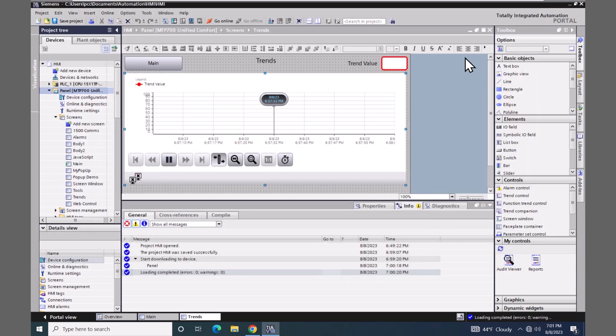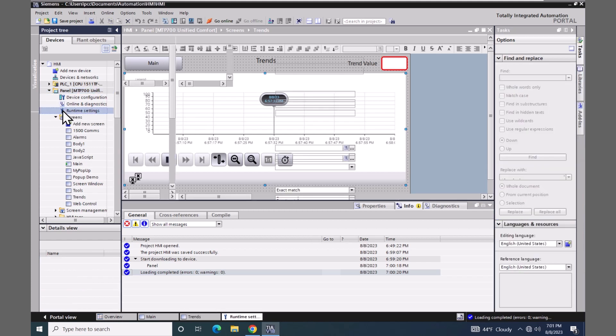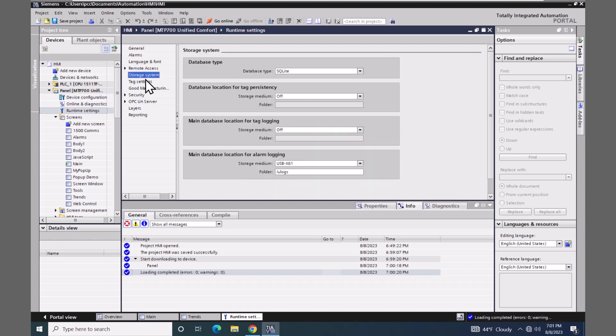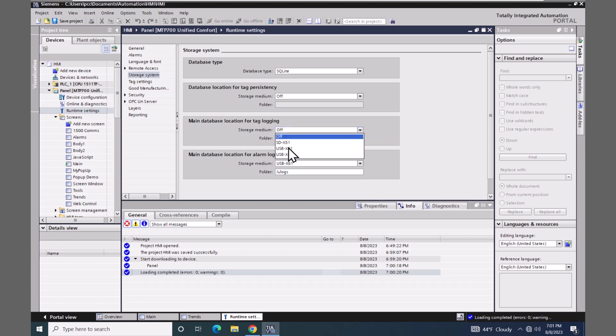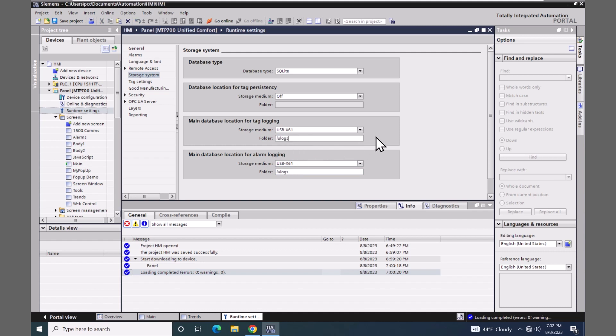Now I will minimize the runtime system and we will convert this to a historical trend. The first thing I will need to do is configure a data log, but I have to enable it. So I will go to the runtime settings, storage system. And the main database location for tag logging is currently set to off. I will select the USB stick X61 and enter in the ulogs path. This is the main database location for the tag logging system.